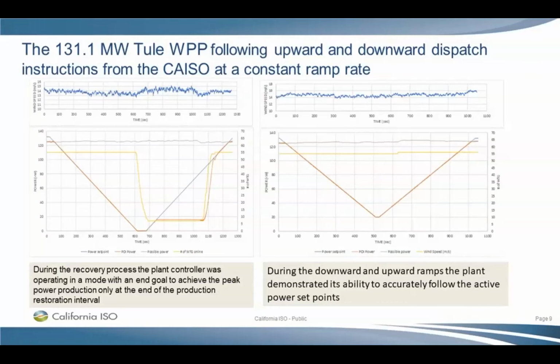So if you look at this first slide, this is looking at a ramp rate on a wind resource, and there are two different ways you can operate here. If you look at the one on the left, it shows a set point. Here we took this plant all the way down to less than 20 megawatts, and then increased it back up to about 115 megawatts. The way this plant could operate, it could meet the set point. If you look at the set points, which form our V shape, compared to the wind trajectory, you can see it was able to ramp down and ramp up to meet the end set point.